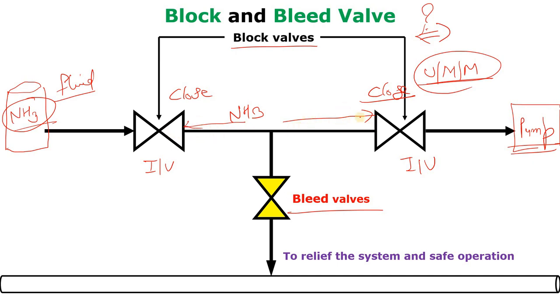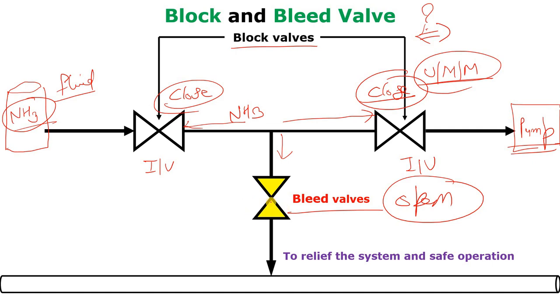So when we close both the block valves, there is a provision — there is a line which we give, and that is the bleed valve line. We will open this bleed valve so that all the ammonia or any explosive and toxic gas will be drained. All the trapped ammonia or any other gas will go from here through this line.